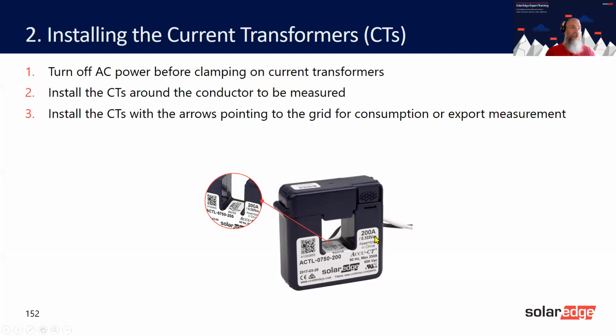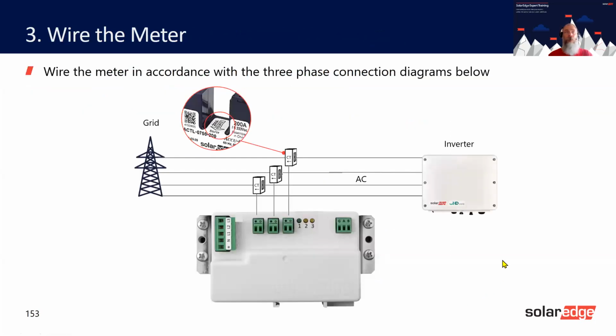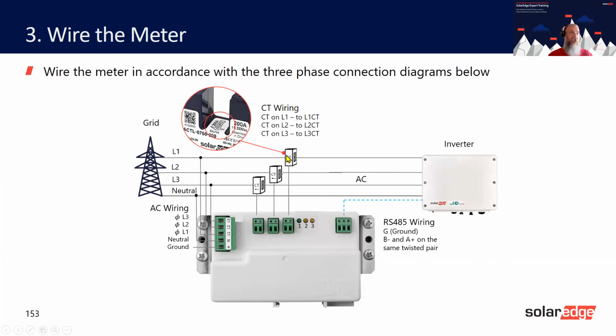It says on here what the rating is, 200 amp. And we've also got this arrow you see here pointing to source. So remember, if we're doing import and export, that needs to face the grid. If we're doing consumption, then this would point to the load that you want to measure the consumption for. Okay. Then placing of it, as we said, arrow pointing towards the grid, making sure that we've got the correct CT, so CT1 on phase one, and also that phase one is wired to phase one as well. If you get those phases incorrect, it will cause some misinformation on the dashboard.